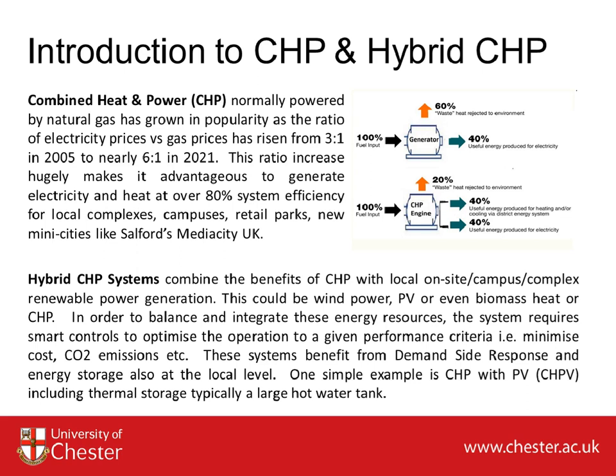Overall system efficiency is over 80%, and in ideal conditions, it can be 85%. On average, in practice, engine efficiencies run somewhere between 80 and 85% efficient, which I think everybody would have to agree is rather more efficient than a gas-fired generator on the national grid. And that is a huge motivator for end users and the nation, and in particular for our carbon emissions.